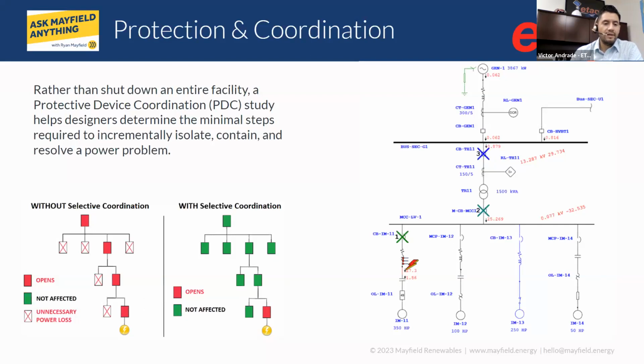These are the red squares. Those are protective devices that opened. So if the system is not properly coordinated, it could bring down your whole system, right? A fault on the low voltage side can go all the way up to your main and essentially bring down the whole site, the whole operation.